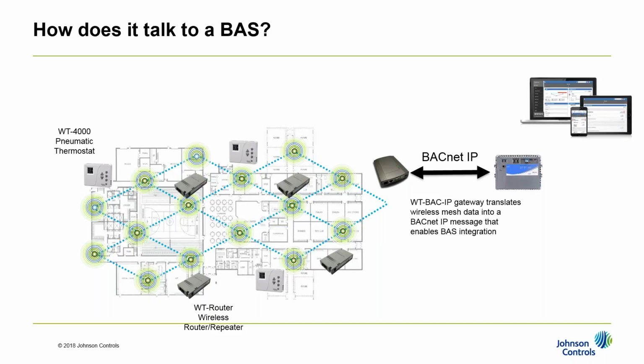Looking at the diagram on your screen, we see the WT4000 pneumatic thermostat, which we consider an end device. In between, we have the WT router, which routes the signals as the name implies, think of it as a signal repeater or range extender. Finally, we have the WT BACnet IP, which is the brains of the system, taking all the data and feeding it over BACnet IP back to your BAS controller, be it one of our Johnson Controls NAEs or a Tridium controller, anything that accepts the standard BACnet IP protocol will work with it.